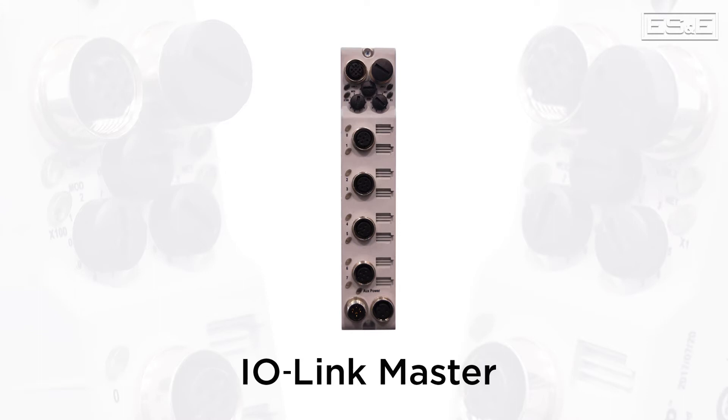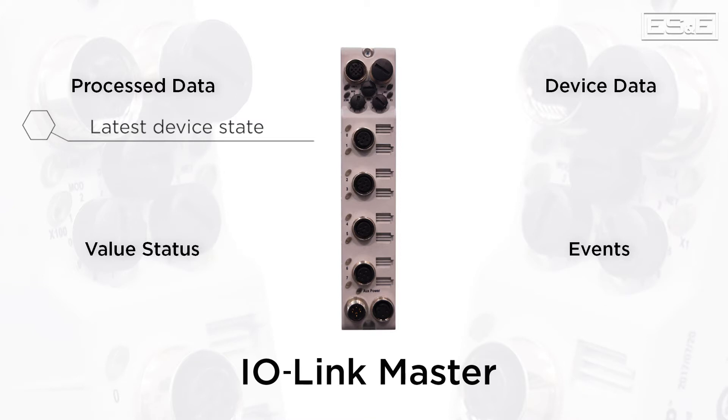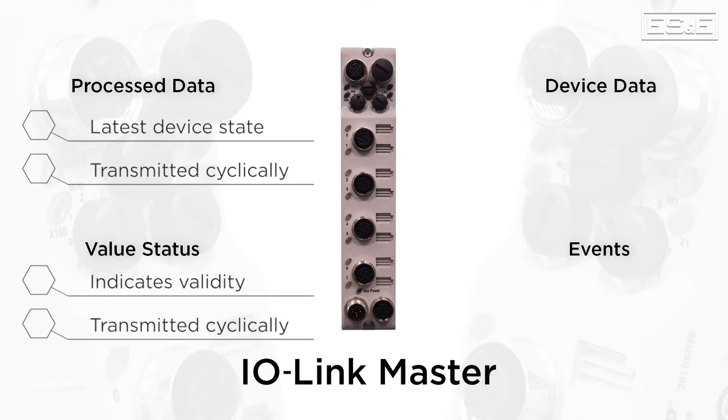IO-Link devices have four types of transmission: process data, value status, device data, and events. The process data is the latest state of the sensor or actuator, such as the speed. Process data is transmitted cyclically, which means it is sent automatically at a regularly defined interval, which is defined by the PLC. The value status indicates whether the process data is valid or invalid and is transmitted with the process data cyclically.